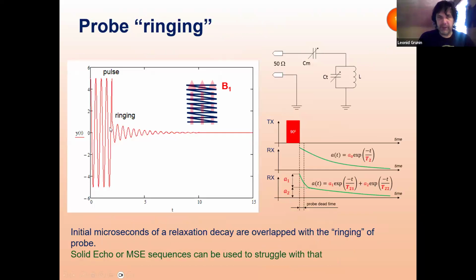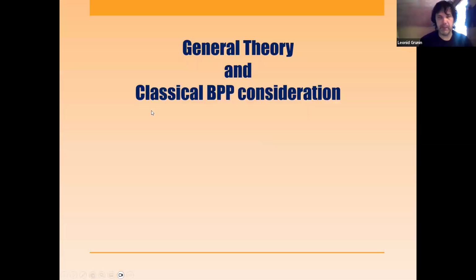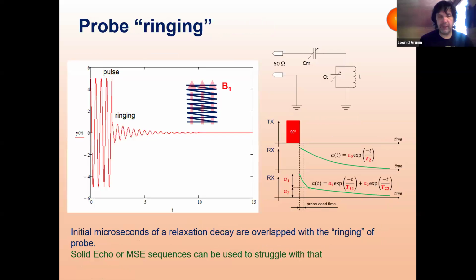If you apply a very strong pulse, then for some period of time the probe, the coil within the magnet, has its own relaxation period, and it should come to equilibrium. Normally this is within 5 to 10 microseconds for a 10 millimeter coil. There is a ringing of the probe. This ringing brings some problems when you are looking at solid samples, but we will discuss this. For many years there have also been techniques to overcome this problem. So that was a very brief introduction.